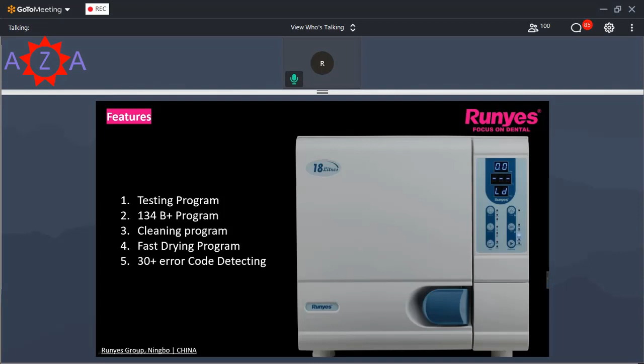Yeah, you can see this is the most popular model, the LED type. It looks very simple, and the operation interface is simple to operate and very friendly. But it combines multiple programs in all our autoclaves. For the testing programs, we have the Bowie-Dick test and the Helix test program available for the penetrability test. It is to verify the steam penetration in hollow instruments and the air removal capacity of vacuum sterilizers. And another test is the leakage test. It is to monitor the vacuum pump performance.